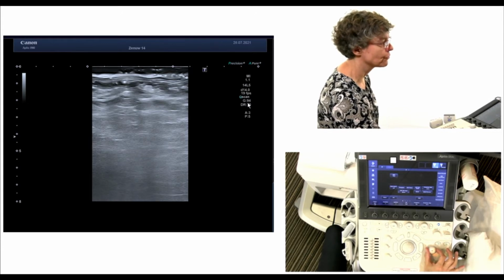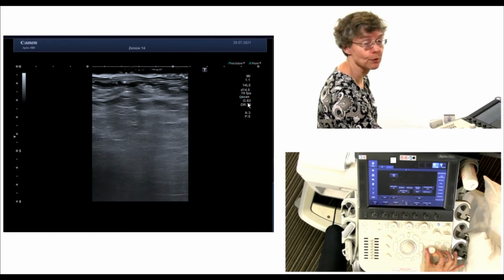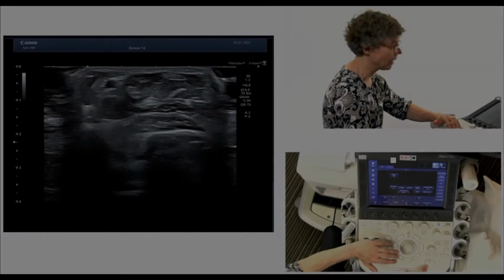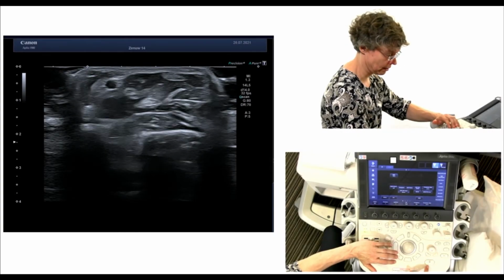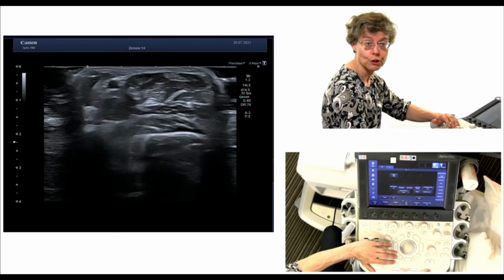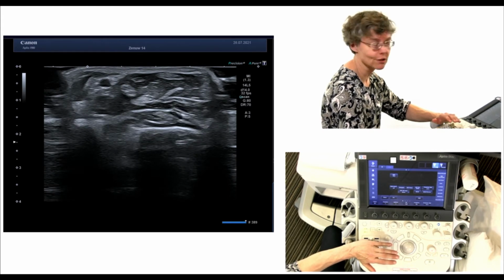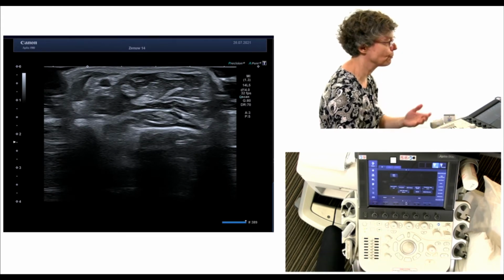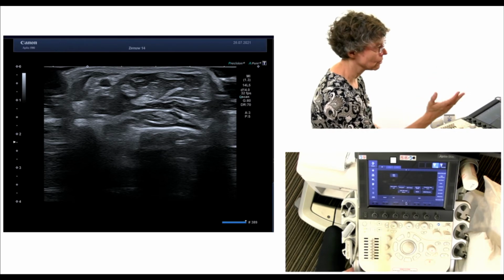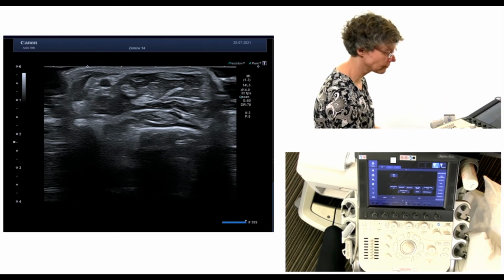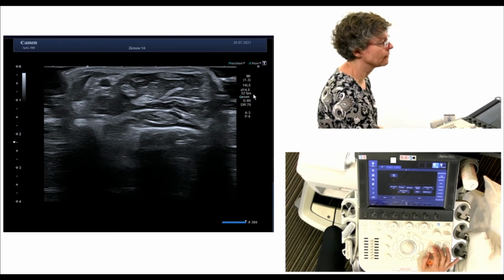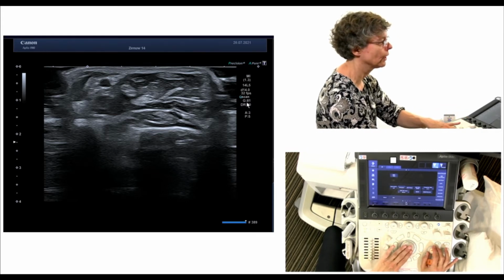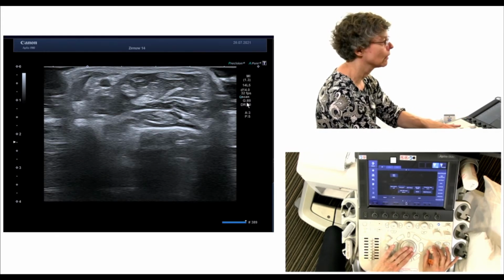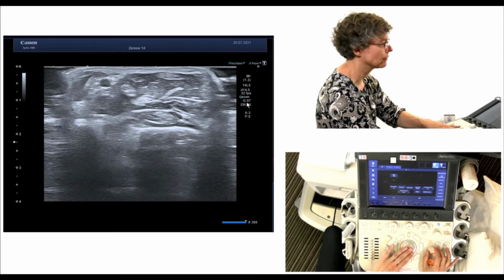Okay, if I turn this knob back, you can see the screen going darker, meaning I'm adjusting the volume and tuning it down. I'm capturing the image that's now on the screen. In this case it's FRZ, which is short for freeze or capture. If you push that, the image is still and you can start doing things on this screen. If I turn up the gain again, so we were looking here at 80 to 100, you can see the whole image becoming brighter, right?